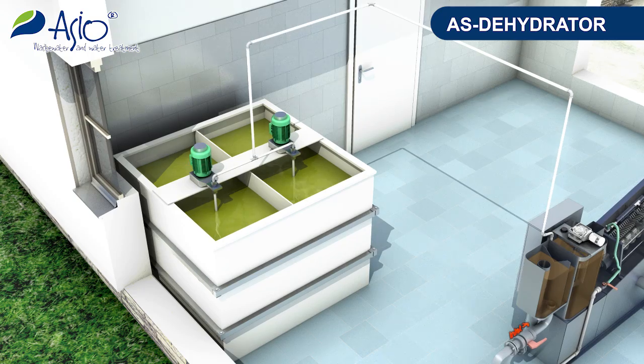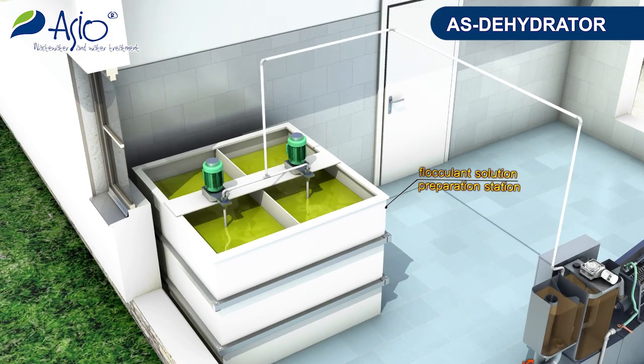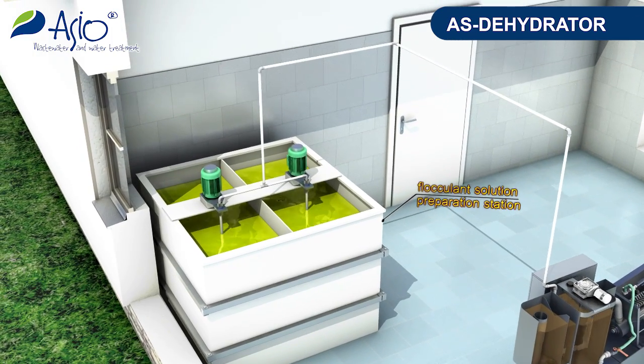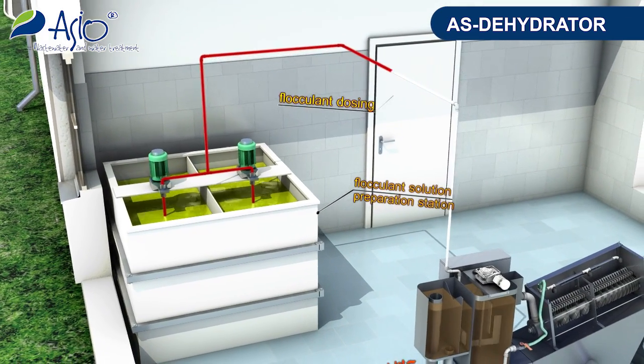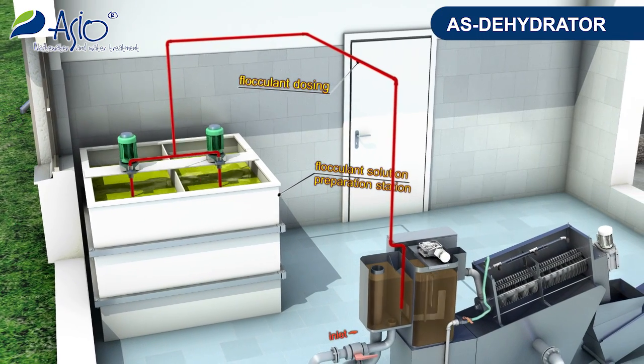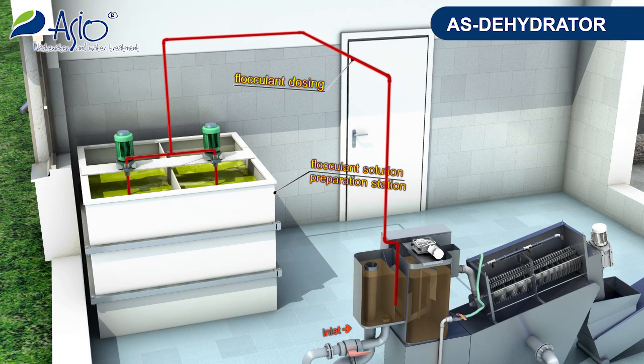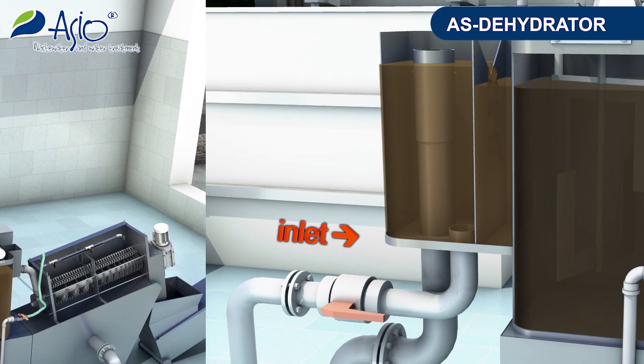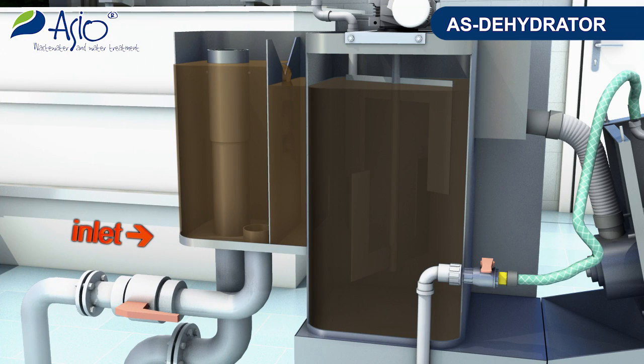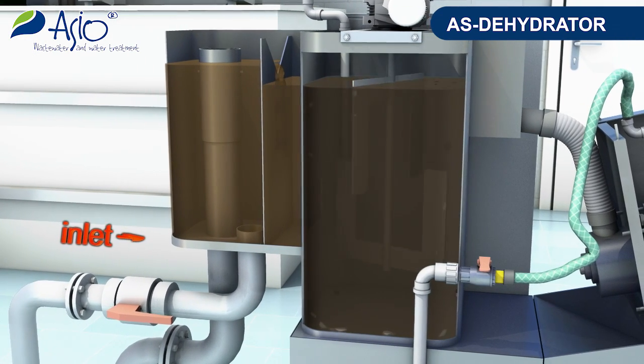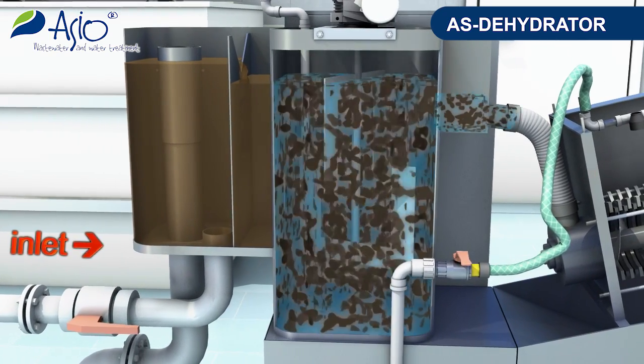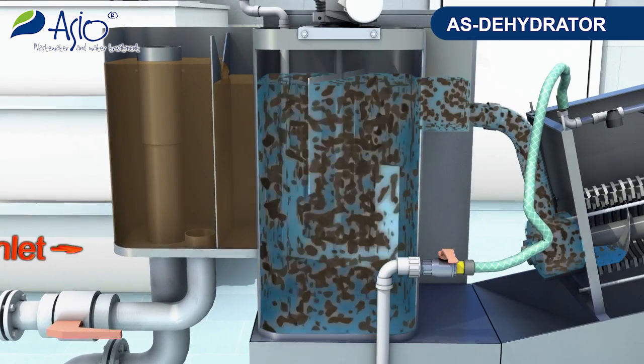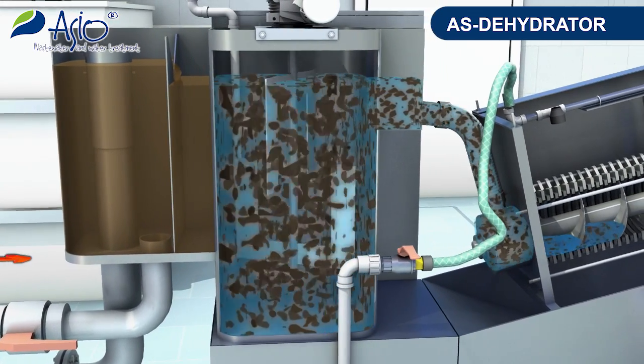The flocculation tank is stirred with a low-speed paddle mixer and a polymeric flocculant is dosed into the incoming sludge. The flocculant solution is prepared directly at the wastewater treatment plant by mixing the concentrated reagent with water in an independent tank, then dosed in sufficient quantities by a dosing pump. The reaction of the flocculant with the sludge causes clearly defined flakes to be formed in the flocculation tank and subsequently brought into the dewatering drum.